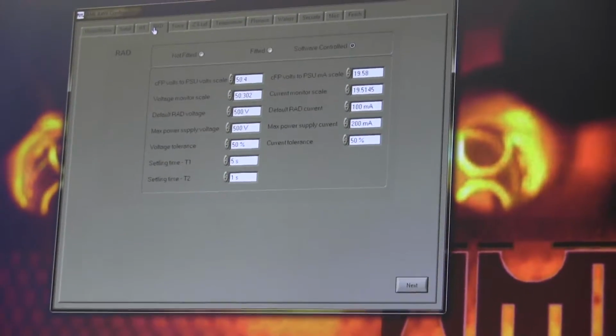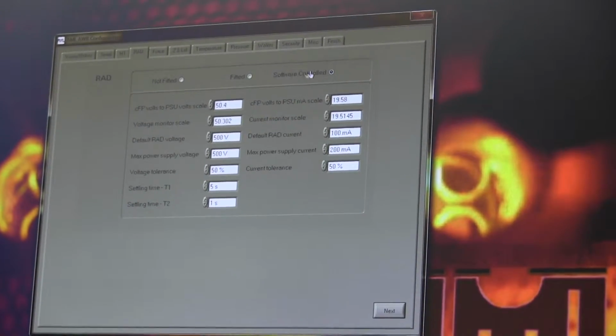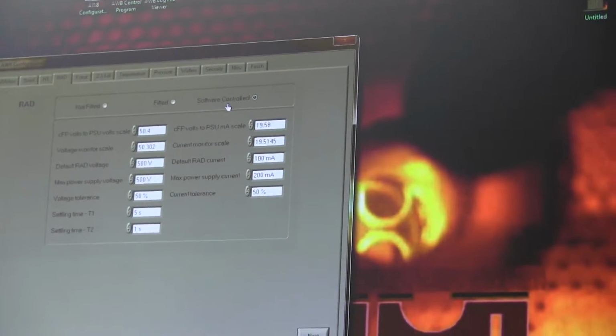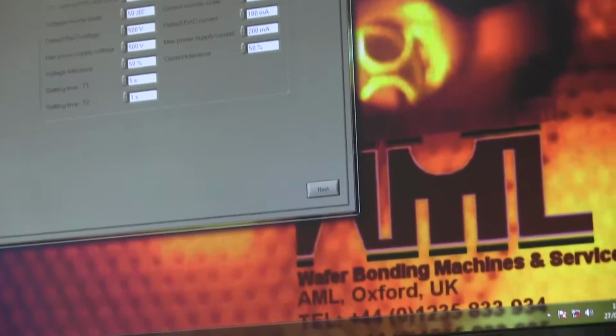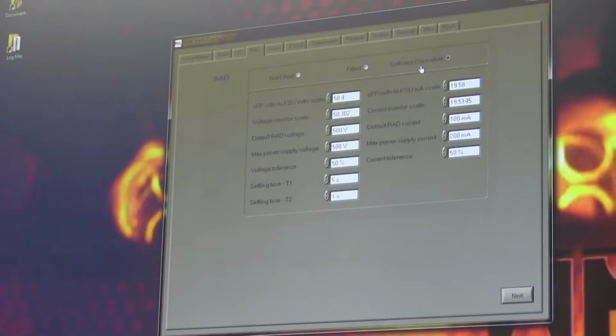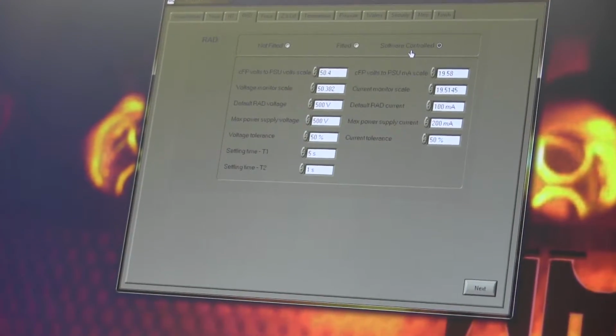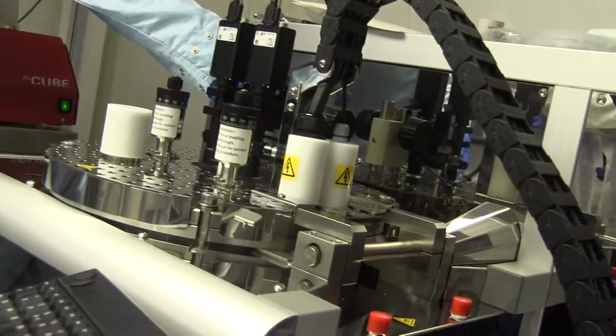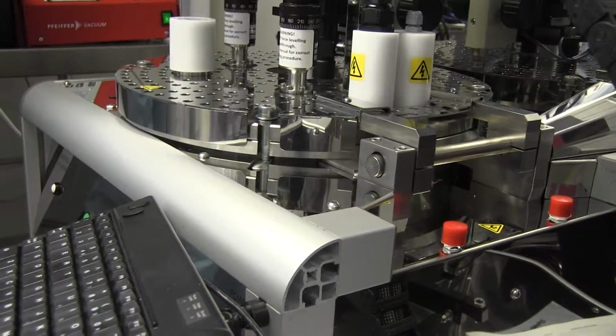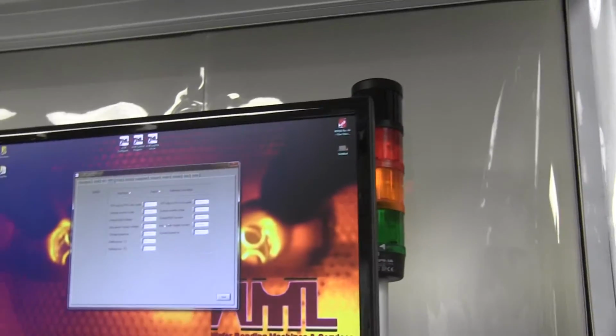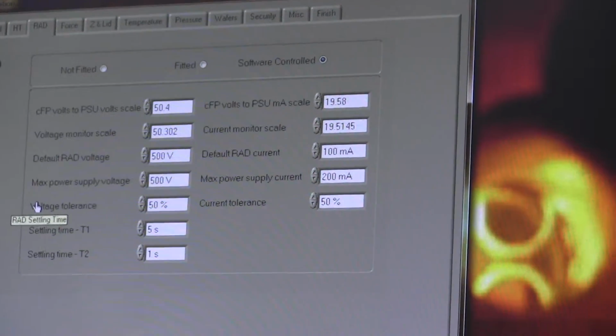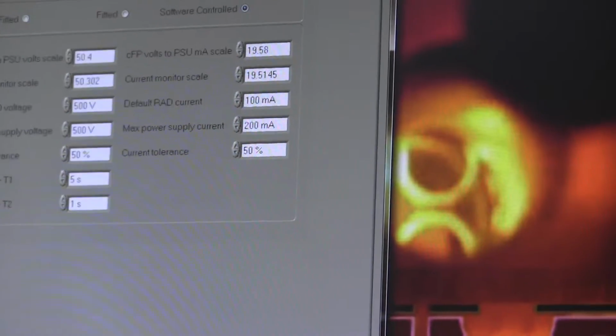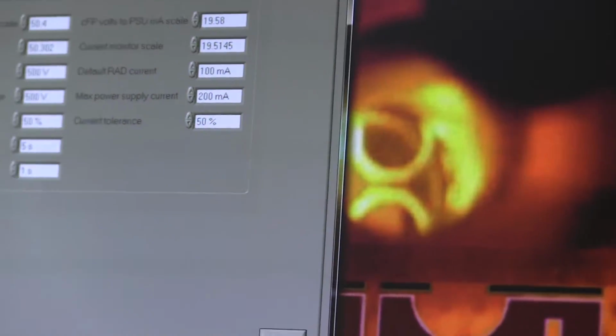RAD, the plasma system. There are 3 options. We have either fitted, not fitted, or software controlled. Some machines that don't have the plasma system have not fitted. On older machines, it was accomplished with a kind of manual control. Up here there was a toggle switch, a couple of LCD screens, and pots for setting the voltage and the current. Modern machines like this one are all controlled via the software. So yours is software controlled. Similarly, we have other parameters. These first 4 are scaling parameters, so that when you ask for 500 volts, you get 500 volts. When you ask for 100 milliamps, you get 100 milliamps.